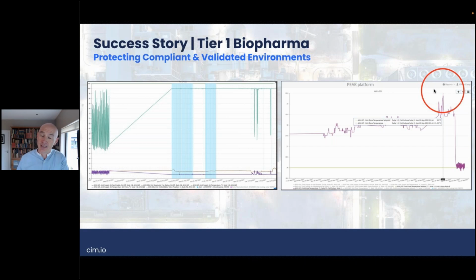But what can happen in an instance like that is if that area goes above that 24 degrees, it's potentially a non-compliance, and in a validated area, where you're making product, it can result in quality getting involved and maybe production being stopped for a while. So the BMS was flagging level 1 and level 2 alarms as the temperature was increasing, but again, that opportunity to get out ahead of this issue was lost in the white noise that was BMS alarms.